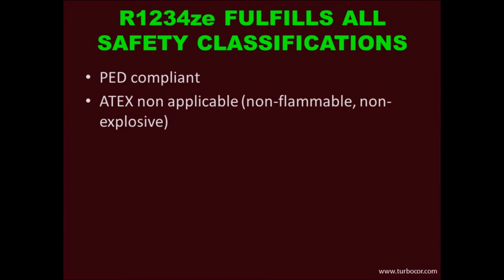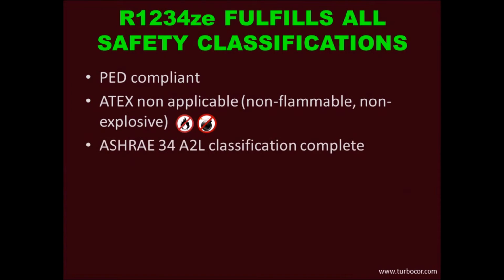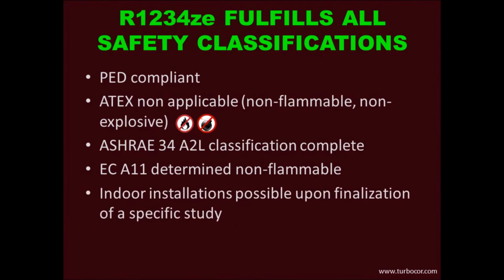French ATEX related to explosive atmospheres is not applicable, as the test demonstrated that the refrigerant is non-flammable and non-explosive. As a conclusion, the Danfoss Turbocor compressor fulfills all safety classifications. A conservative position is to install units only in outdoor places. Indoor installations are possible after finalization upon a specific study.